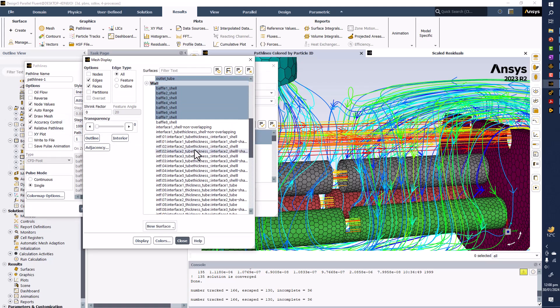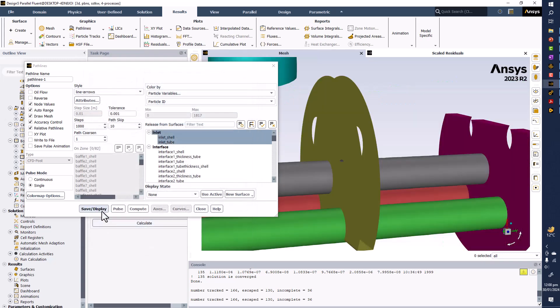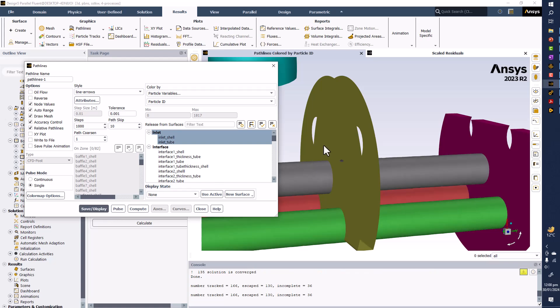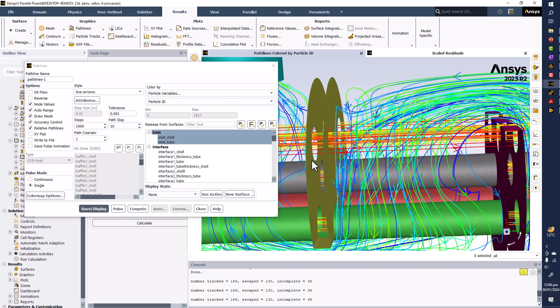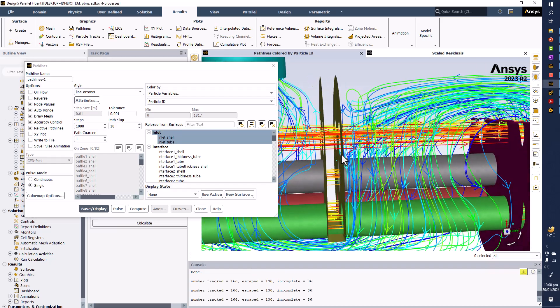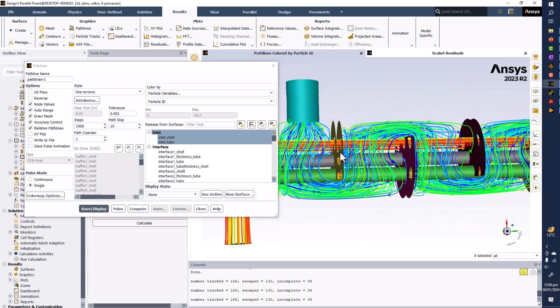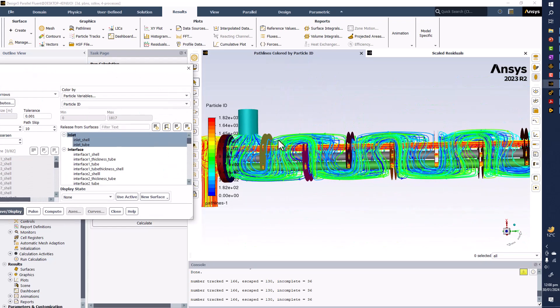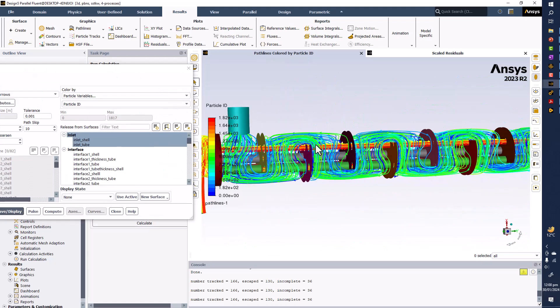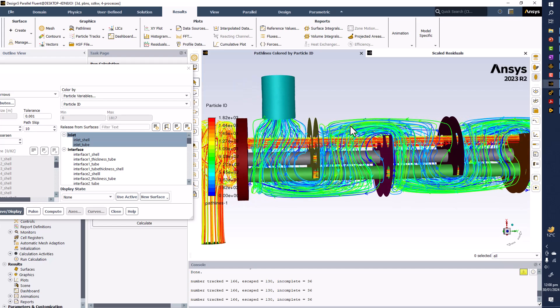If I show all the baffles, including baffle number eight, this will look like this way. We can see that baffles are basically making the flow also in the cross and it takes more time to move through it, but definitely this will increase the pressure losses, but at the same time it will increase the heat transfer rates.